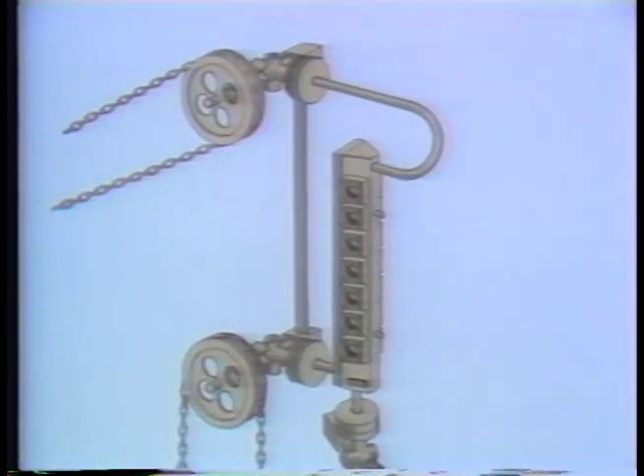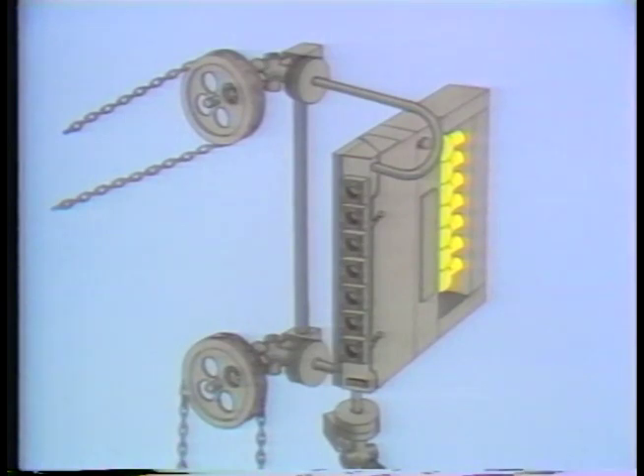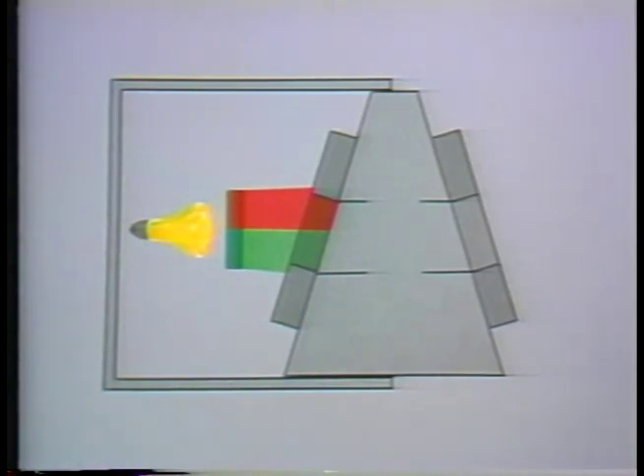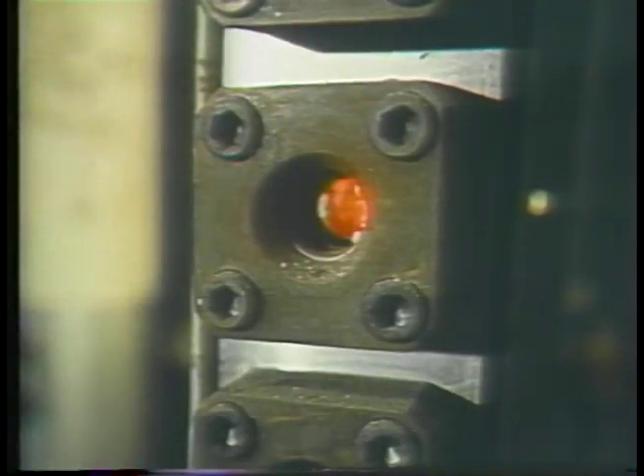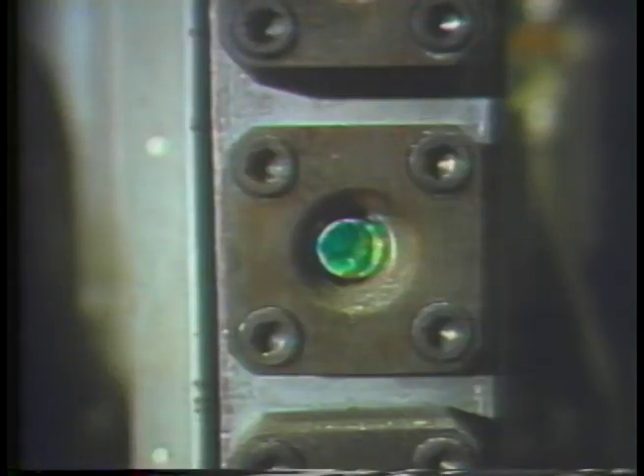Multiple-port gauge glasses can appear empty because the fluid level is not visible when it is between ports. Sometimes special illuminators are used to solve this problem. The illuminator has red and green screens that color the light reaching the gauge. The light bends differently depending on whether there is water or steam in the gauge glass — steam causes only red light to come through, while water causes only green light. Therefore, ports above the water level shine red, and ports below shine green. This type of illuminator is sometimes used on flat gauge glasses as well.